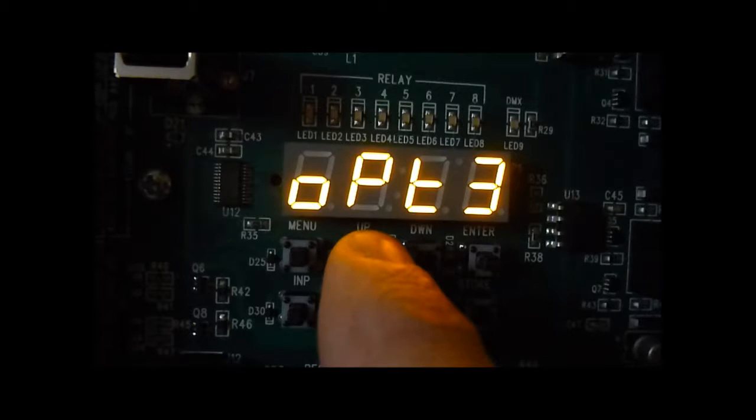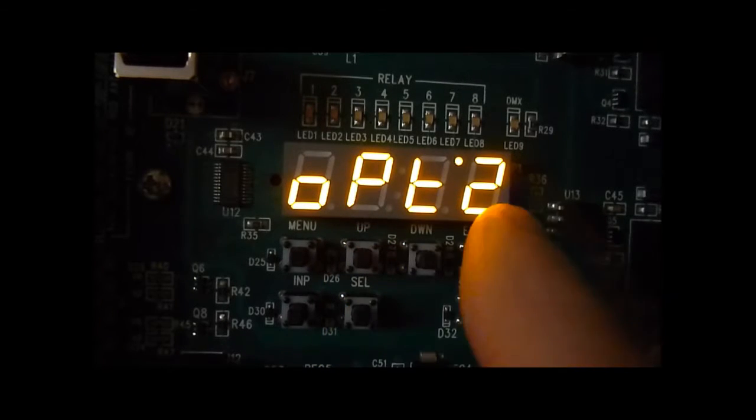Receptacle mode ignores any daylight sensor input and also any high and low trim. To change the configuration for the load type, we'll just select one of these three options. Press select to change it to a switch type and press store.